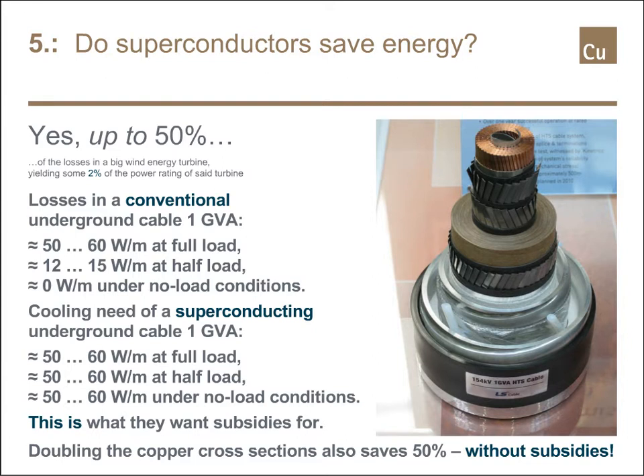And they also try to promote superconducting high voltage and extra high voltage cables. And I always wondered how much energy you need to cool them down permanently to 100 Kelvin, 90 Kelvin, 80 Kelvin, which are their operating temperatures. It took me years to find out finally that it was about 50 to 60 watts per meter. Now, I calculated the losses in a conventional cable, and I ended up with something around 50 to 60 watts per meter at full load. And when you halve the load, then the ohmic losses, of course, drop to a quarter. And when the cable is running energized but without any load, then there are hardly any losses at all, while the cooling demand in the superconductor will always be there. Now, I wonder where the savings are. Actually, they are not there at all.